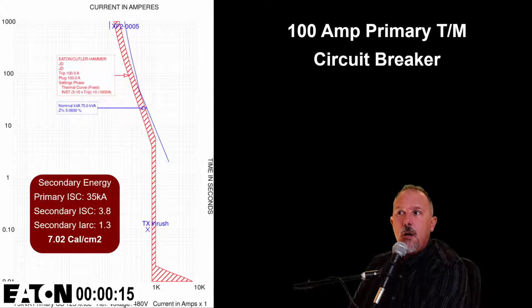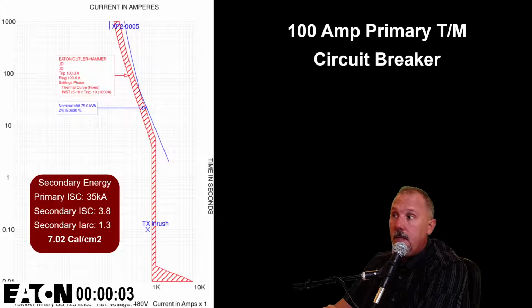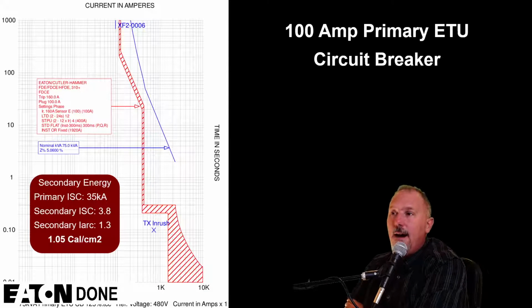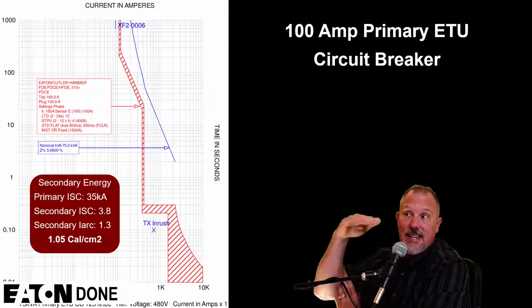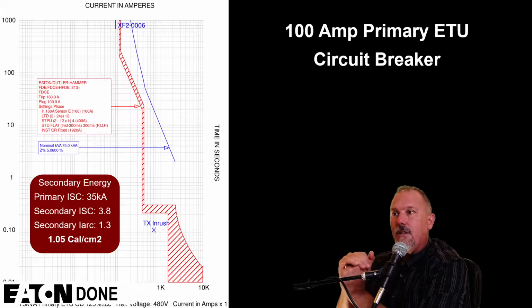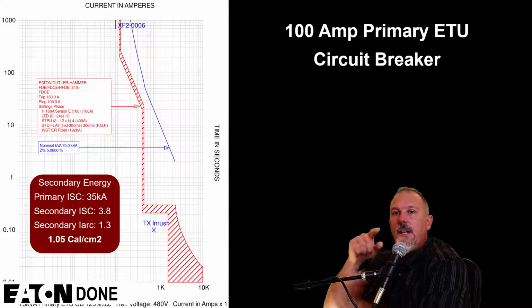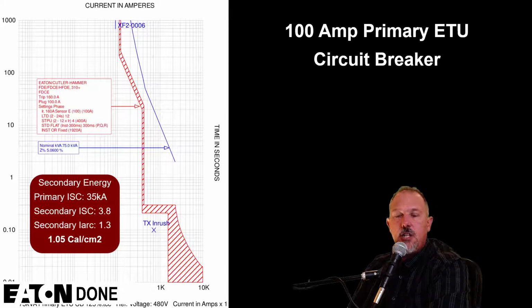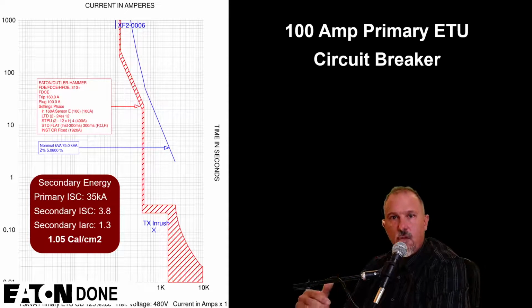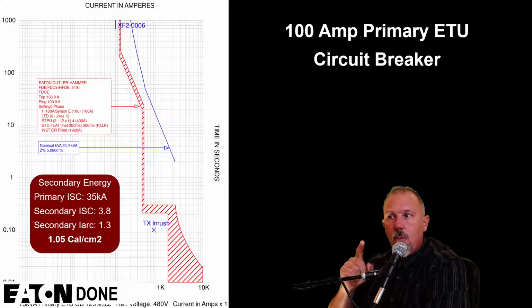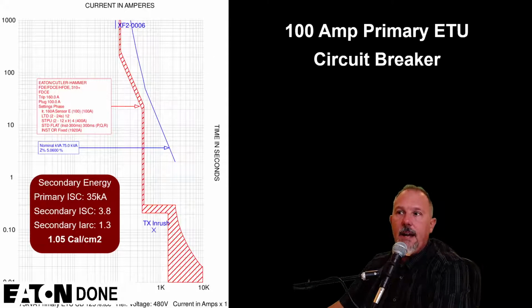But look, I put a smaller overcurrent device and I get the same amount of energy, 7.02 calories. Why? Because 500 and some amps is much less than the instantaneous pickup, even of that 100 amp thermomagnetic circuit breaker. I did a 100 amp electronic trip unit and voila. Now, you'll notice the short time delay isn't as fast on this one, so I get a little bit more incident energy. But the moment you get an electronic trip unit, if you specify this, talk to our application engineers in the field, there's a very good chance you can get an arc reduction maintenance switch, and I highly recommend an arc reduction maintenance switch on the primary of any transformer that you install for your electrical worker who's going to be doing work on the secondary of that transformer.